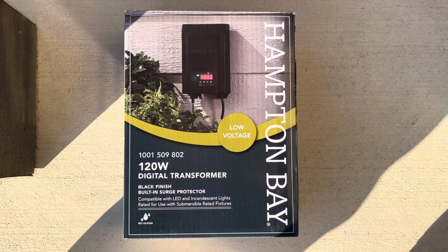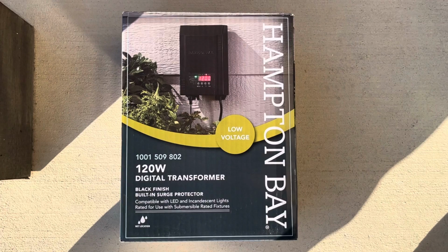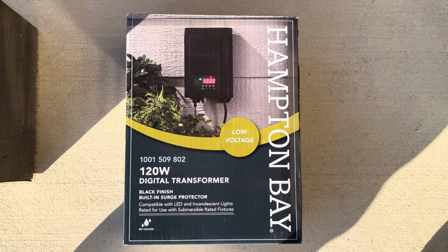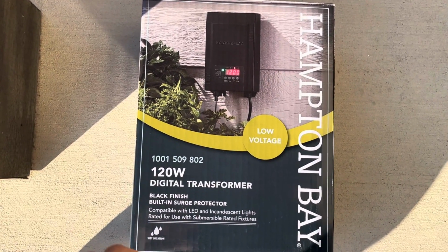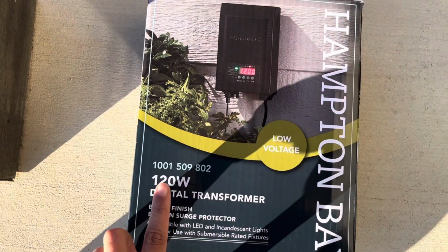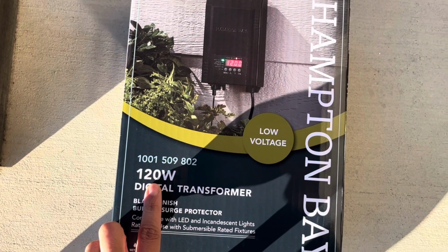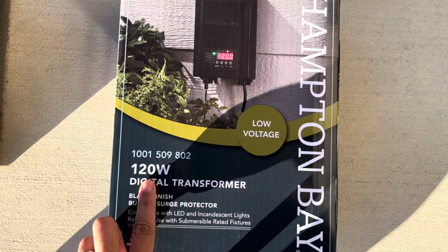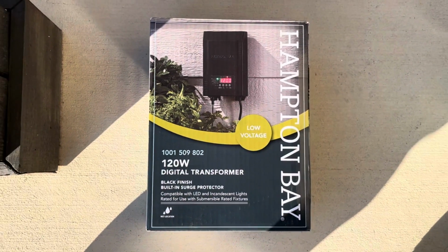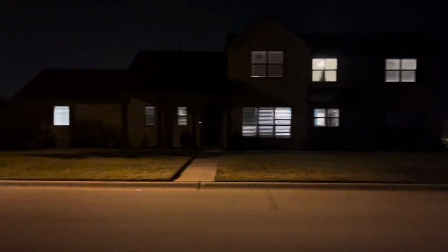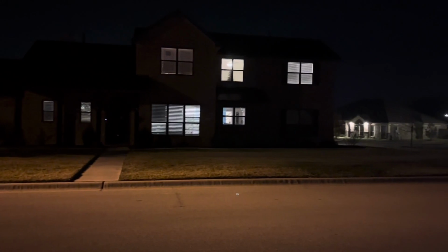I selected this 120 watt transformer because I only intend to connect 7 lights at about 10 watts each, so I only actually need a 70 watt transformer. But it's better to size up a bit to ensure adequate voltage along your entire cable. If you don't, this could lead to lights not being bright enough or even flickering.